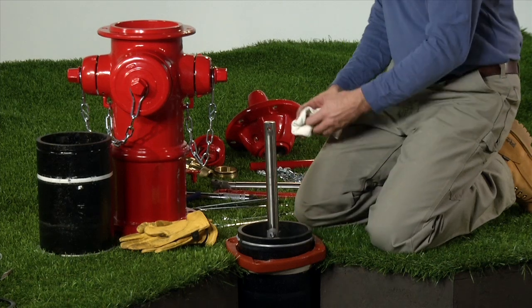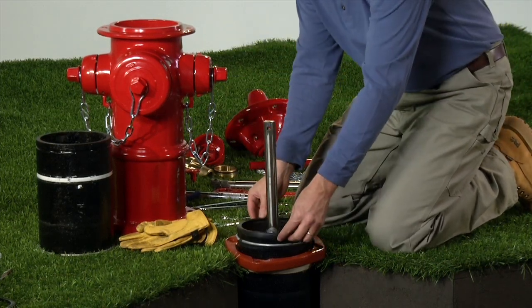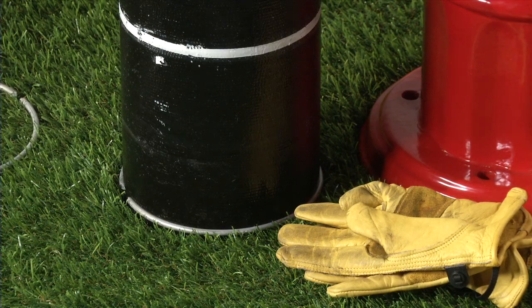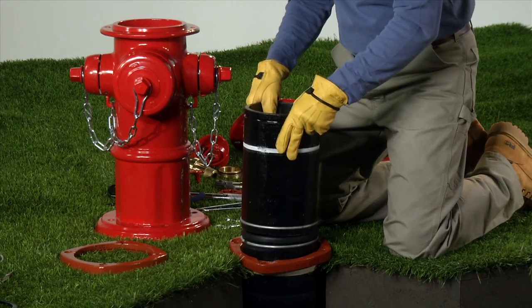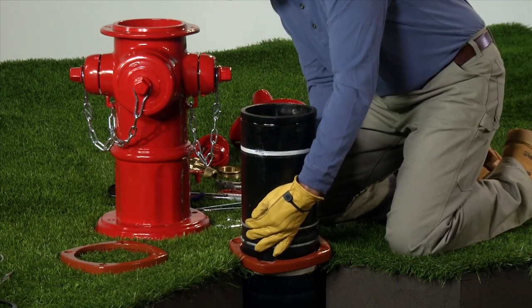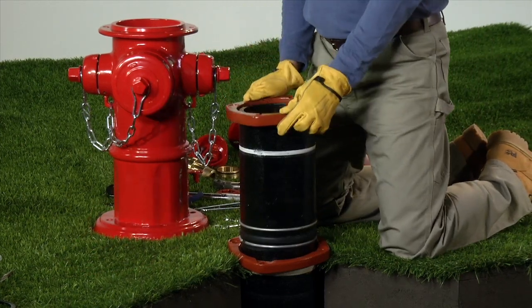Clean the top of the lower barrel and install a barrel gasket. If not already done, install a lock ring onto the lower groove of the extension barrel. The top of the extension barrel is marked with a white bury line. Place the extension barrel onto the lower barrel, making sure that the barrel gasket stays in place. Slide the standpipe flanges until they rest against the lock rings.